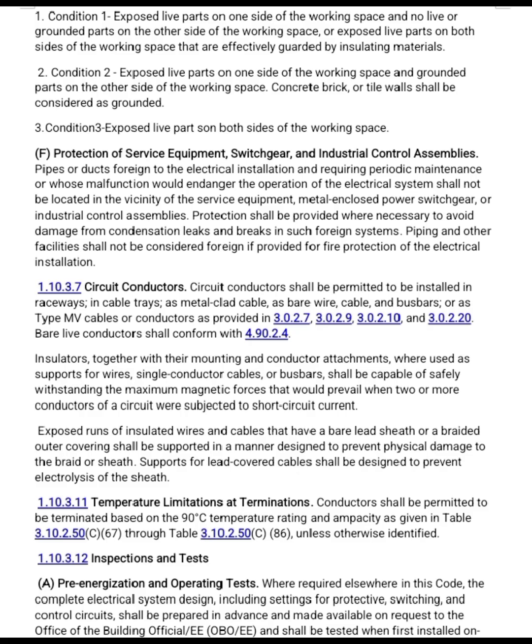Single conductor cables or bus bars shall be capable of safely withstanding the maximum magnetic forces that would prevail when two or more conductors of a circuit were subjected to short circuit current. Exposed runs of insulated wires and cables that have a bare lead sheath or braided outer covering shall be supported in a manner designed to prevent physical damage to the braid or sheath. Support for lead-covered cables shall be designed to prevent electrolysis of the sheath.